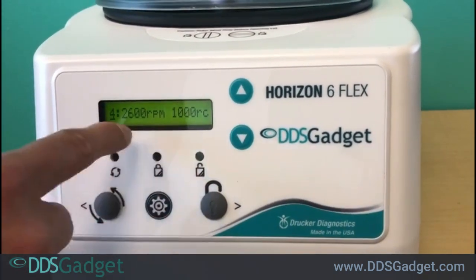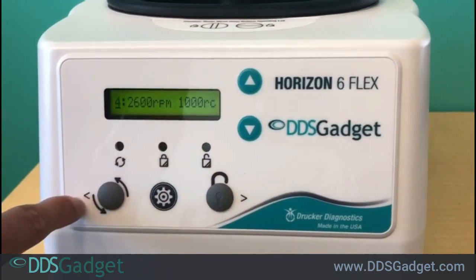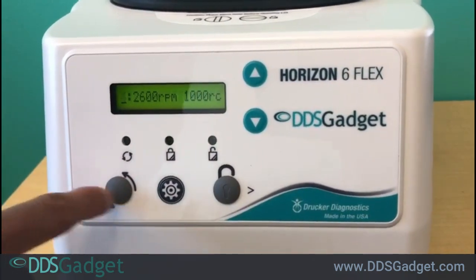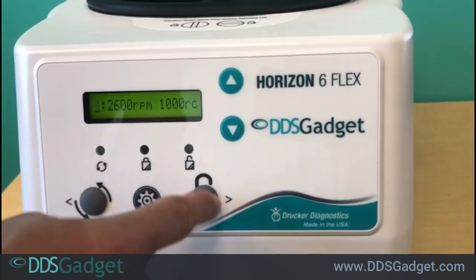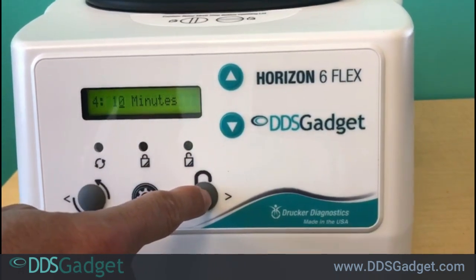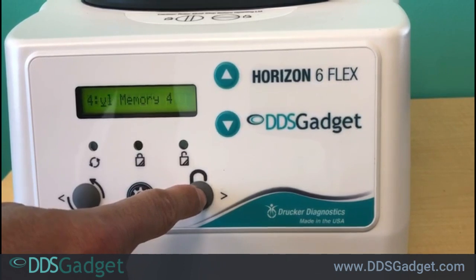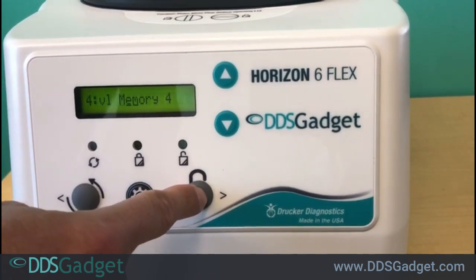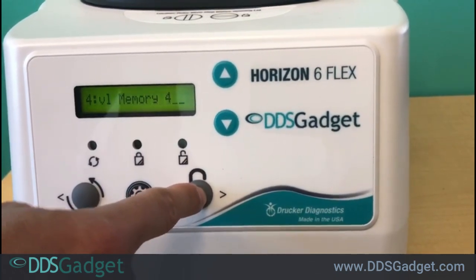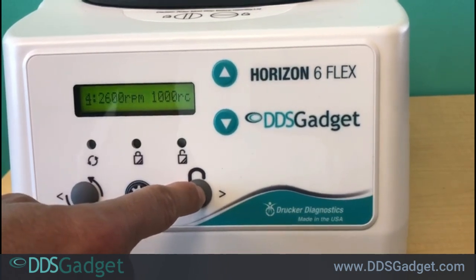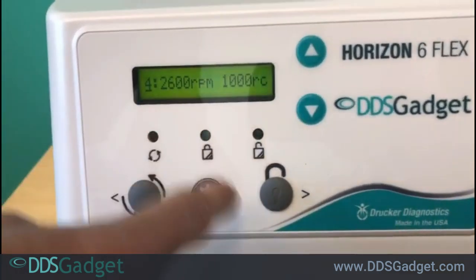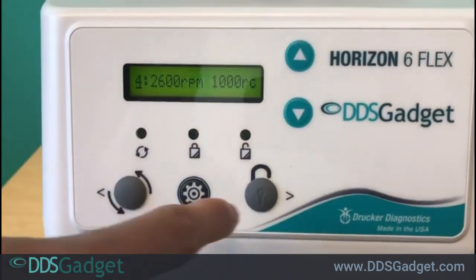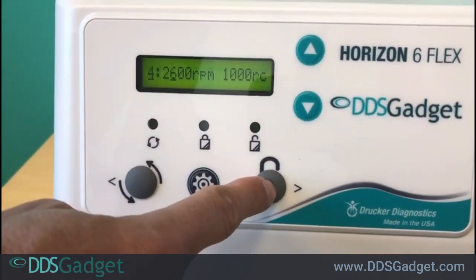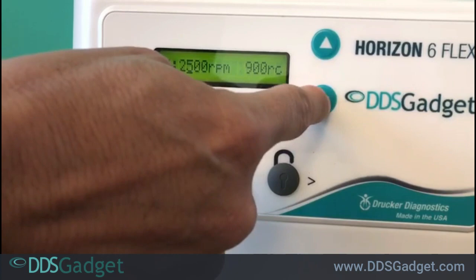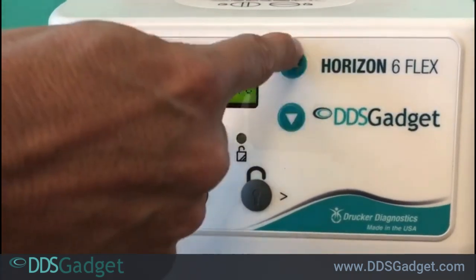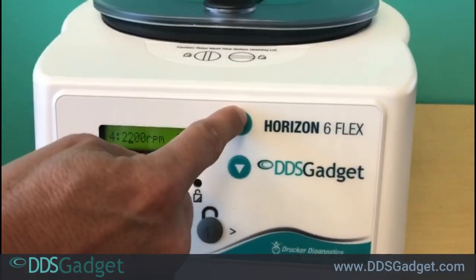And you move through the different customization settings by moving the right and left arrows, which is the start and lock button when you're in the gear mode. So you could see as we cycle through, there's the minutes, the braking, the beeper, and the name. Let's go through again. So we have over here, let's say we press the gear cycle, we now want to change the RPM time. So we move the right arrow to the RPM time, and we can move it up. That's down, sorry, or we can move it up.